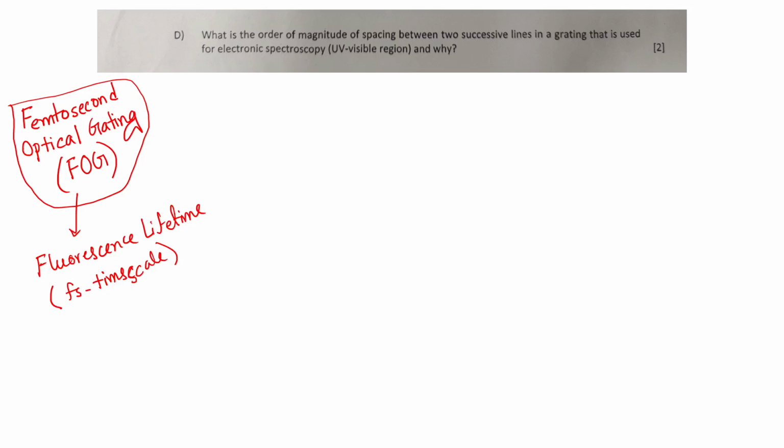Even if you are using an ultrafast laser whose pulse width in time scale is 100 femtoseconds or even less, the minimum instrument response function that the instrument can record would be in picoseconds, 60 or 70 picoseconds, even with a very high-end instrument.